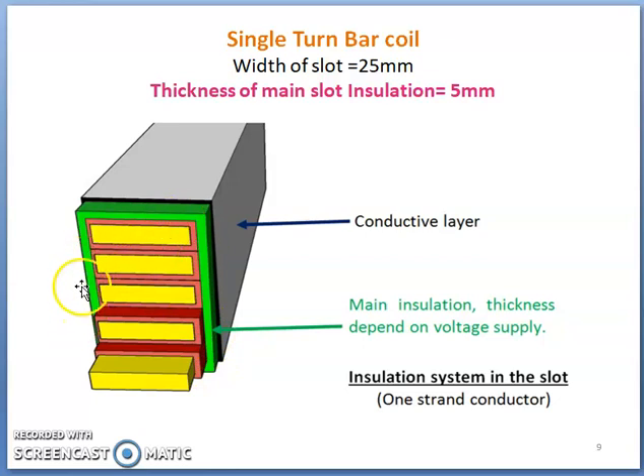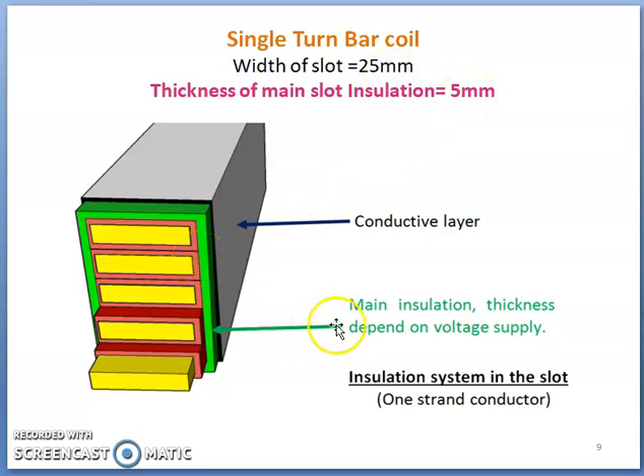In single turn bar coils, the width of the slot is typically 25 mm. The thickness of main slot insulation depends upon voltage. For voltage rating up to 10 kV, the thickness of main insulation is 3.6 mm; for 11 kV it is 3.8 mm; for 16 kV it is 5.1 mm; and for 18 kV it is 5.6 mm. As the voltage of the machine increases, the thickness of main insulation must increase because dielectric strength depends upon thickness of insulation.